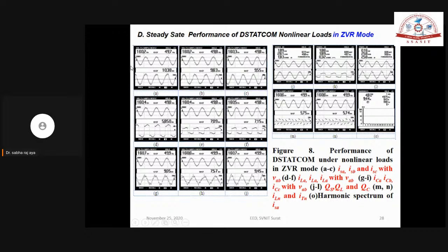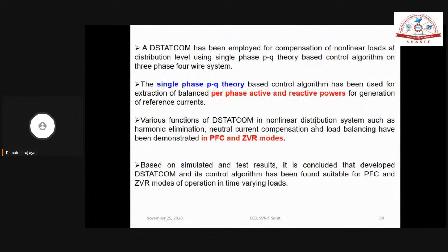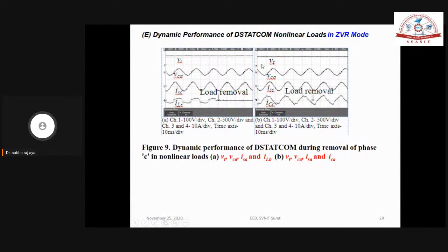So we have compensated the supply voltage up to rated value with less than 5% distortion. That I also want to tell. On the supply side also, the supply neutral is neutral current free. Then also after that you can see the dynamics. Always we can see during load change, during behavior change, how VT and VDC are going to change.